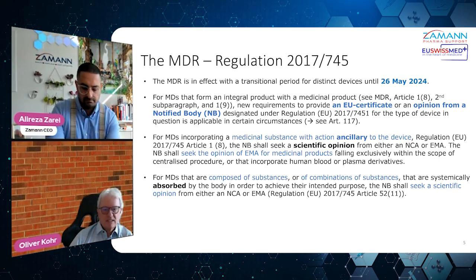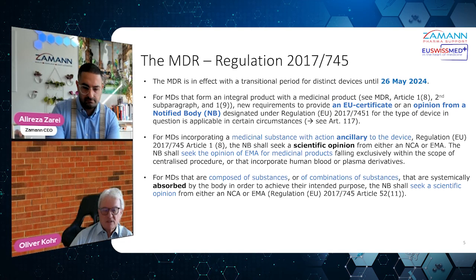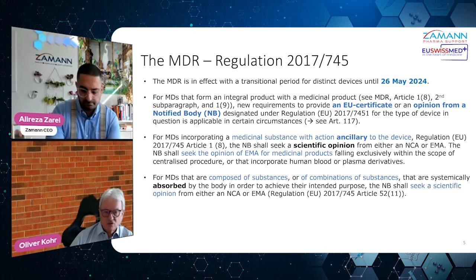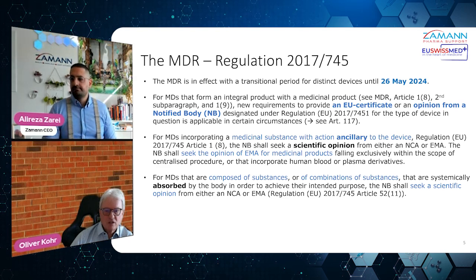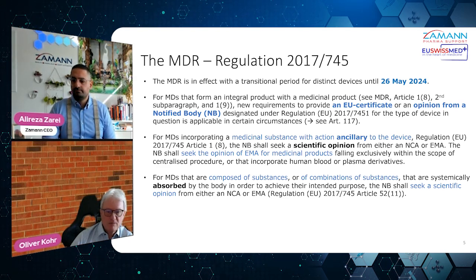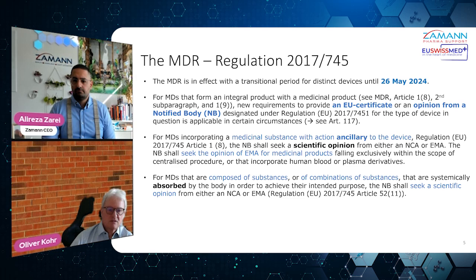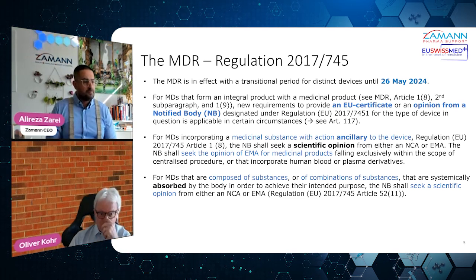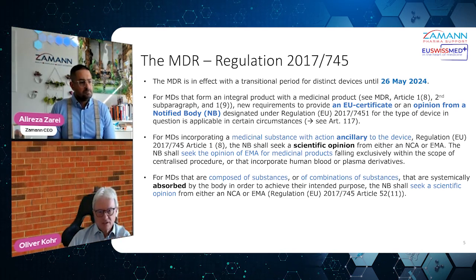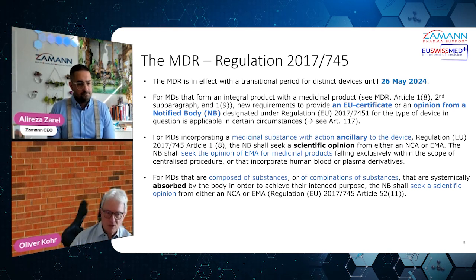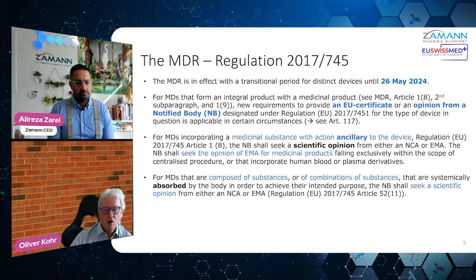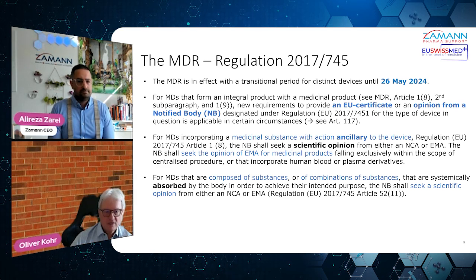If the medicine is ancillary to the device, that means it's not integral, then, of course, you need, now comes the point, the NCA, the National Competent Authority, or EMA, you need a scientific opinion. So you see, for integral it's the EU certificate or opinion from the notified body, which, of course, the EMA also will look through to, or you need a scientific opinion.